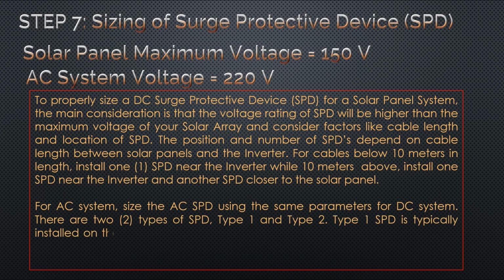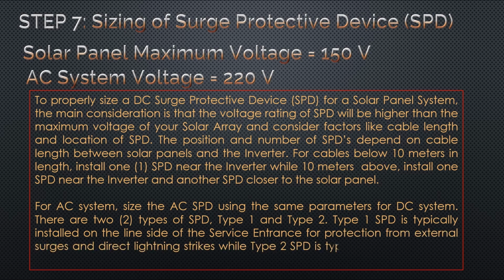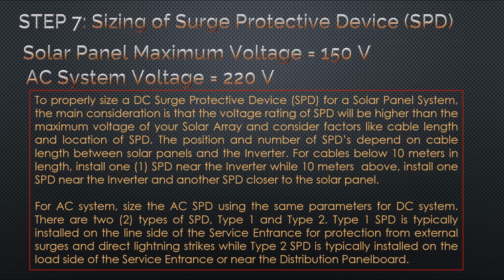The position and number of SPDs depend on the cable length between the solar panels and the inverter. For cables below 10 meters in length, install one SPD near the inverter, while for 10 meters and above, install one SPD near the inverter and another SPD closer to the solar panel. For the AC system, size the AC SPD using the same parameters as for the DC system.